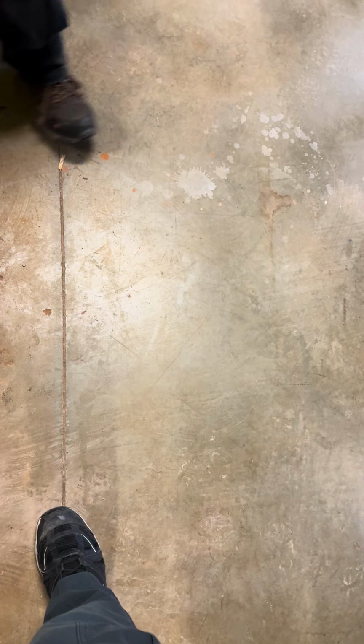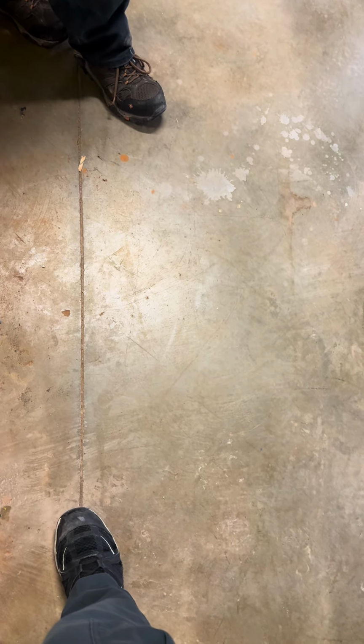So if one month you decide, okay, I'm going to take a sample, you get it tested, and they said, oh, it's down to 73 parts per million. Then you're going to go, well, how did that happen? Chances are you've had a leak in the building. Okay? The pressure's gone down, you notice that, oh, we're still at 50 psi, but you have a regulator that's tied into the city hot cold water that automatically fills the system up to keep it at 50 psi.